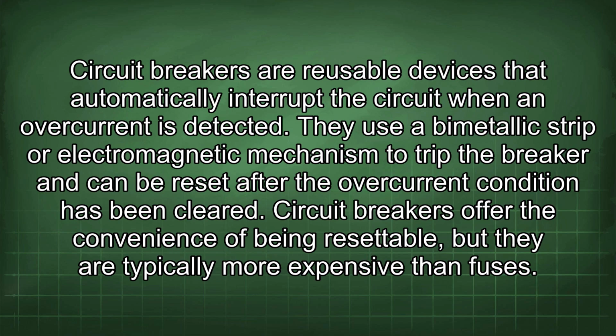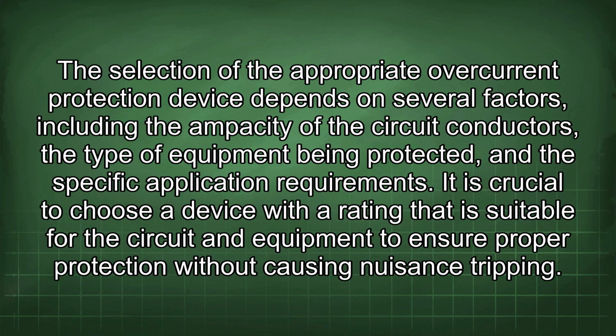Circuit breakers are reusable devices that automatically interrupt the circuit when an overcurrent is detected. They use a bimetallic strip or electromagnetic mechanism to trip the breaker and can be reset after the overcurrent condition has been cleared. Circuit breakers offer the convenience of being resettable, but they are typically more expensive than fuses. The selection of the appropriate overcurrent protection device depends on several factors, including the ampacity of the circuit conductors, the type of equipment being protected, and the specific application requirements. It is crucial to choose a device with a rating that is suitable for the circuit and equipment to ensure proper protection without causing nuisance tripping.